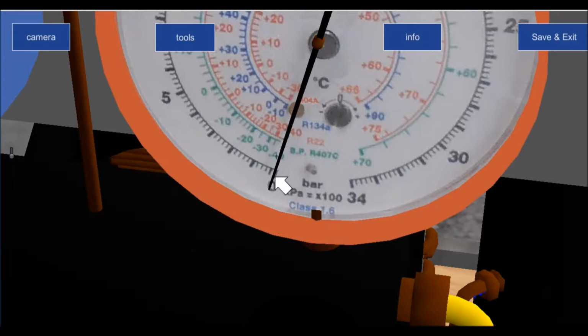If you have a digital, then you're going to have to maybe get it calibrated once a year by a professional company, and send it off to make sure that it's not knocked out of calibration and you are getting correct readings. But it goes back to the other thing that I was saying: you'd be better off investing in a good digital thermometer, and that'll become more obvious in a few minutes when I go through explaining how to use a thermometer, and you only use gauge manifolds as a last resort.